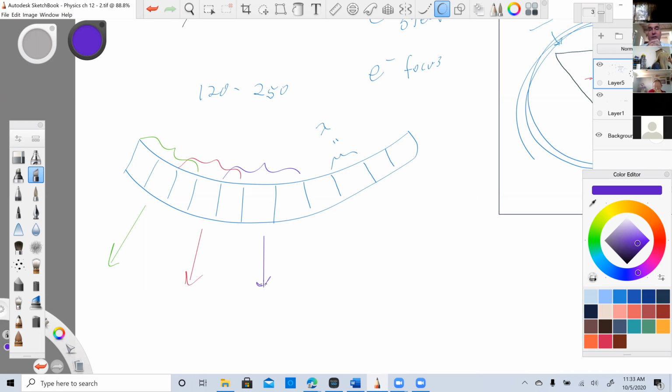So here's the thing about curved transducers. They don't really steer. They don't steer mechanically, and they don't steer electronically. The steering, and I put that in air quotes, is done by the fact that it's a curved transducer to begin with. So the beam is directed straight out of the crystals, but since the crystals are arranged in an arc, the pulses travel in different directions as they radiate out.